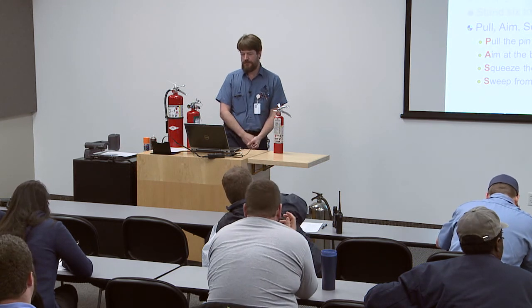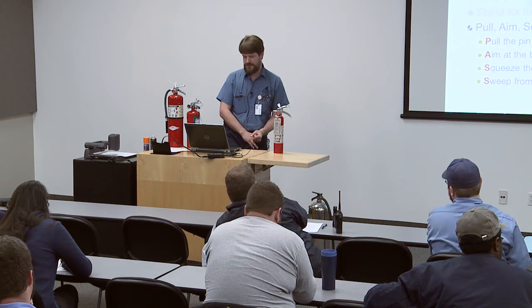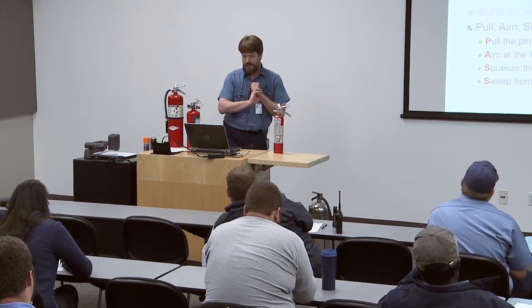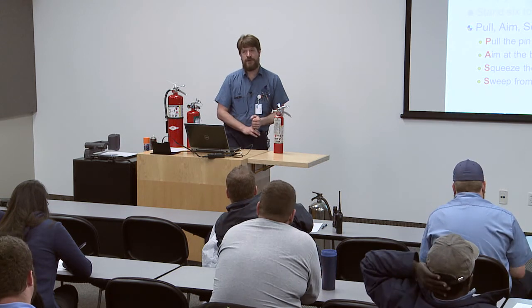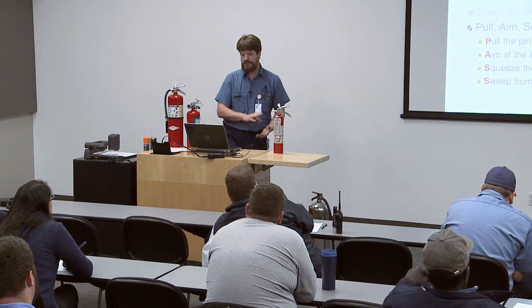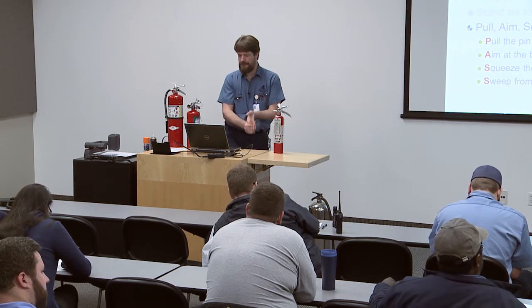Don't spray into a corner. We had someone do that one time. Got a whole face full of extinguishant. It tastes terrible. It's very corrosive. Keep yourself a safe distance. Be very careful in confined areas. You don't really want to breathe this stuff. You pull a pin, aim at the base where the fuel source is, the lowest point of the fire.